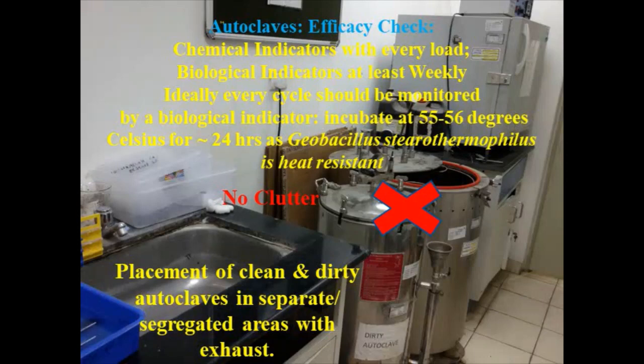And these biological indicators usually have a double jacketed design. The outer vial is a plastic vial which contains the spore strip, and this spore strip is of a very heat resistant bacteria, that is Geobacillus stearothermophilus, but it is killed at a temperature of 121 degrees Celsius for 60 minutes. Usually in 15 to 20 minutes it's killed. So Geobacillus stearothermophilus, being a thermophilic or heat resistant bacteria, this biological indicator should be incubated at a higher temperature, not at 37 degrees Celsius, but at 55 to 56 degrees Celsius.